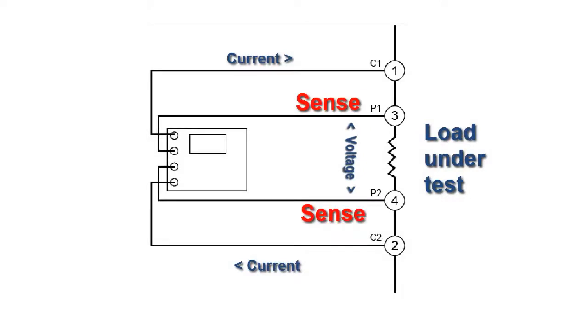The placement of these probes ensures that only the voltage across the load is measured, independent of any resistance contributed by the current or source probes. There is virtually no current flowing through the sense probes. Nearly all the current flows through the source probes. This allows for a high level of measurement sensitivity and accuracy when the load under test is of low resistance.